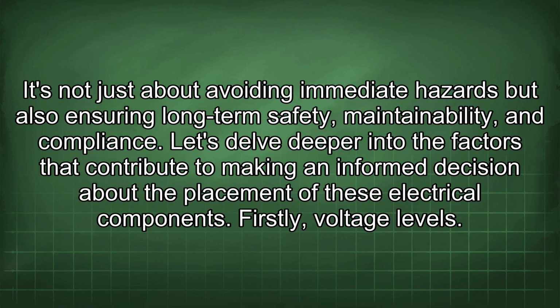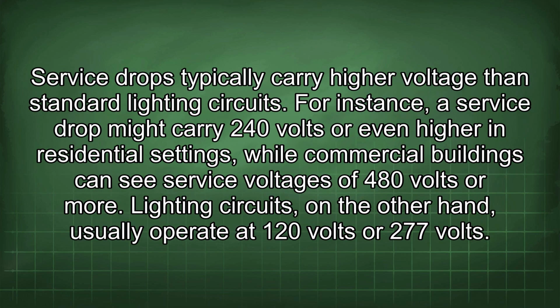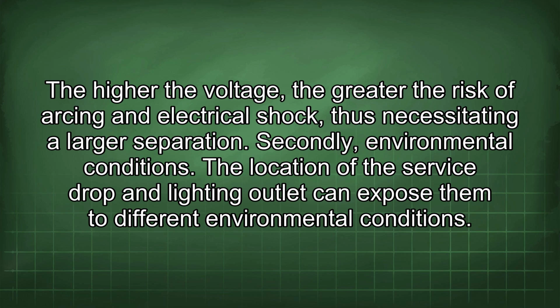Let's delve deeper into the factors that contribute to making an informed decision about the placement of these electrical components. Firstly, voltage levels. Service drops typically carry higher voltage than standard lighting circuits. For instance, a service drop might carry 240 volts or even higher in residential settings, while commercial buildings can see service voltages of 480 volts or more. Lighting circuits, on the other hand, usually operate at 120 volts or 277 volts. The higher the voltage, the greater the risk of arcing and electrical shock, thus necessitating a larger separation.